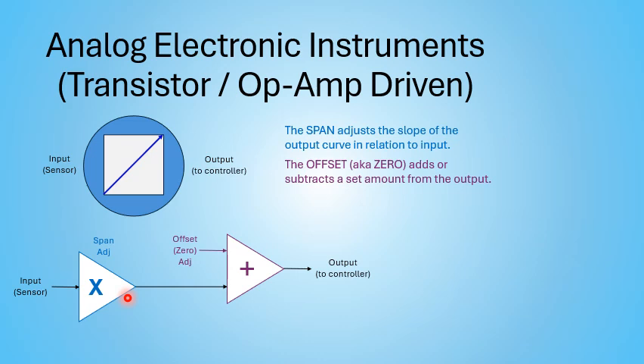And so it was a point of diminishing returns, but the fact they could not compensate for things like temperature, time, etc., made those circuits tend to drift by up to 0.5% per year or more. And that's actually where a lot of our instrumentation calibration standards come from. A lot of plants are still operating at a 1% tolerance. Everything was kind of based on that then. It still is, or sometimes 0.5%. And even your calibration frequencies are based on that in a lot of places. Sometimes regulatory drives that, but so that's the basic problem with the old instruments. In a minute, we'll talk about what's different with the newer instruments.